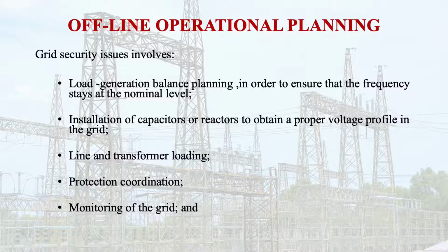Then installation of capacitors or reactors to obtain the proper voltage profile in the grid. That means reactive power compensation for the grid security issue. Then line and transformer loading needs to be checked. They should not be overloaded. So this grid security issue also involves these line and transformer loading issues.